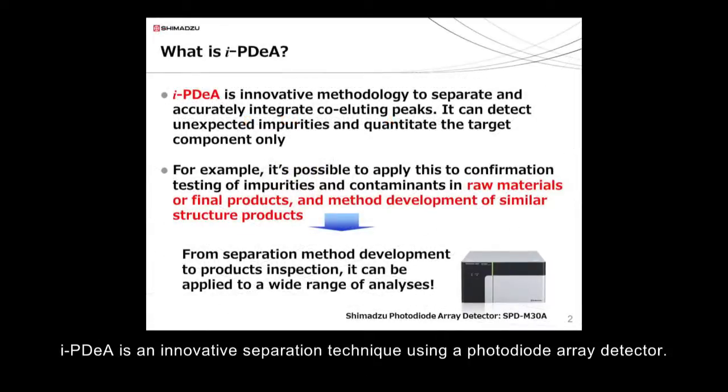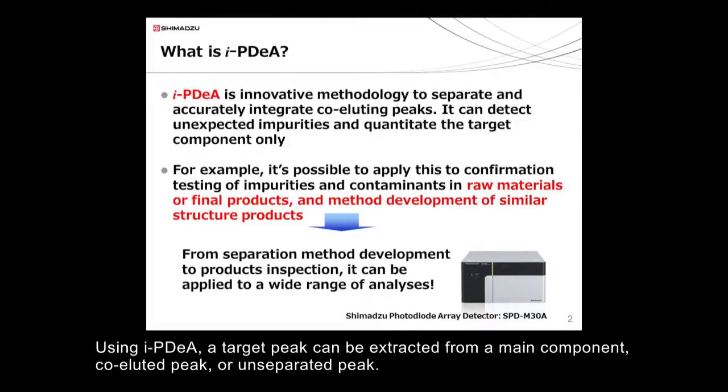IPDA is an innovative separation technique using a photodiode array detector. Using IPDA, a target peak can be extracted from a main component, coeluted peak, or unseparated peak.